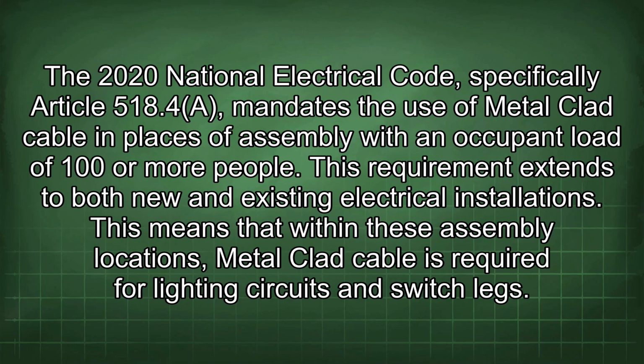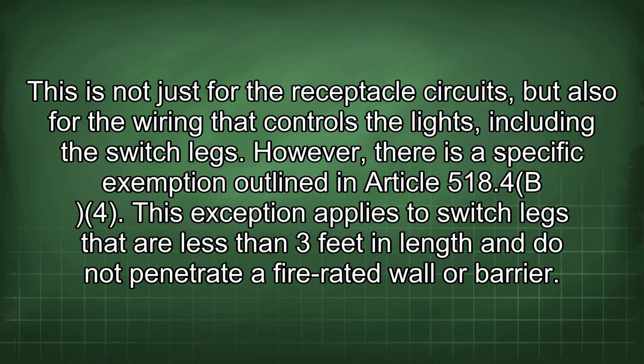The 2020 National Electrical Code, specifically Article 518.4(A), mandates the use of metal-clad cable in places of assembly with an occupant load of 100 or more people. This requirement extends to both new and existing electrical installations. This means that within these assembly locations, metal-clad cable is required for lighting circuits and switch legs.